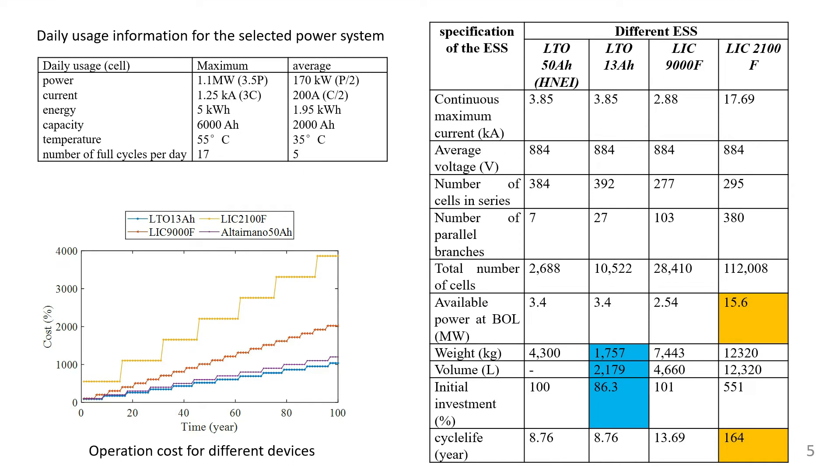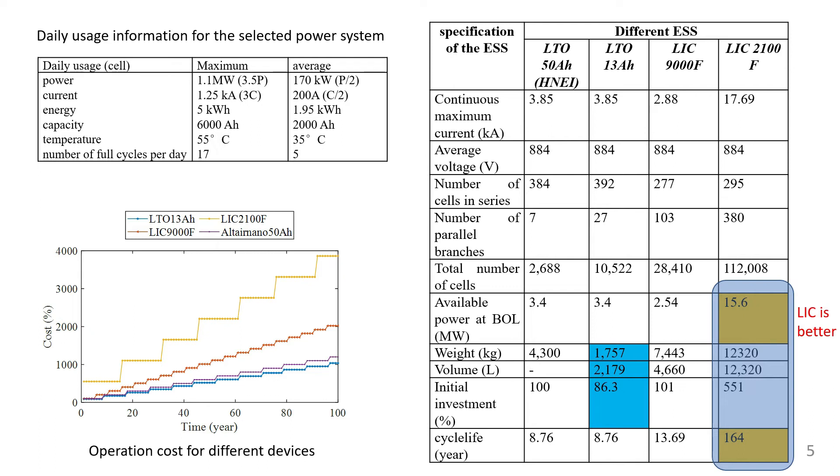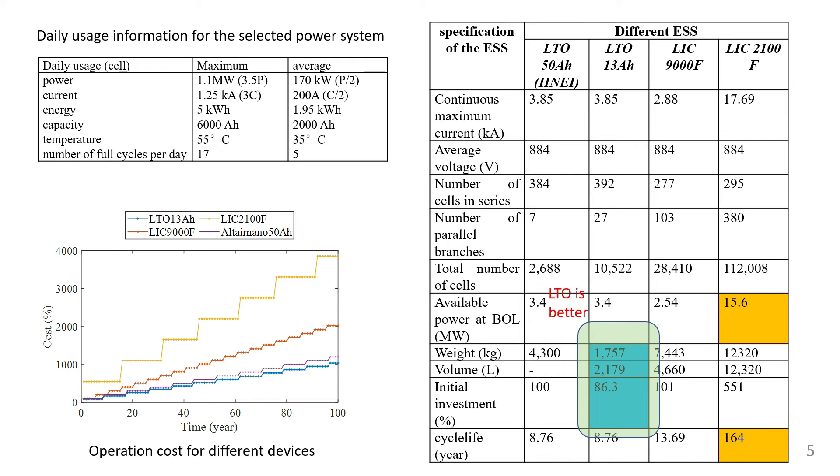Our calculation shows that lithium-ion capacitor has a longer lifetime and higher power capability. However, LTO-based energy storage system is lighter, cheaper, and less volume compared to the others.